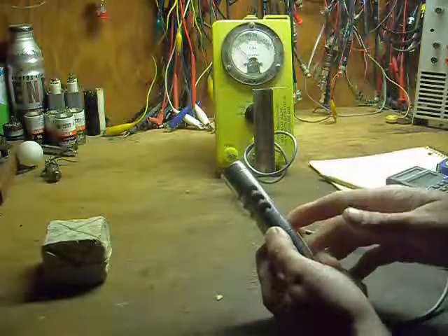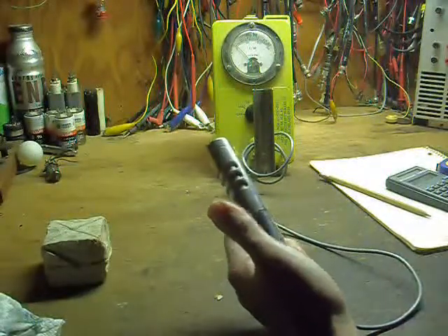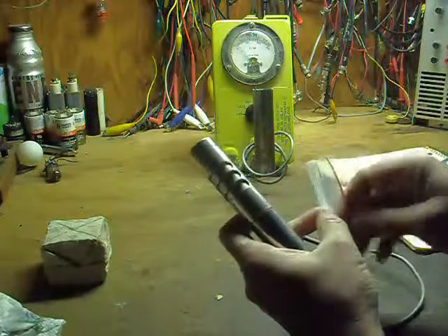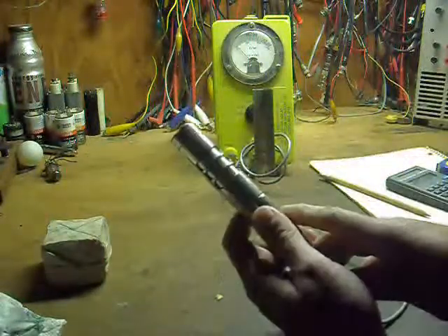If that happens, the probe should be fully disassembled and cleaned. Careful attention should be paid to the Geiger tube. It is fragile and can be damaged easily. To help avoid surface contamination of the probe, you can put a thin plastic bag over the probe, which can be discarded after measurements are taken, to protect the probe from long-term contamination.